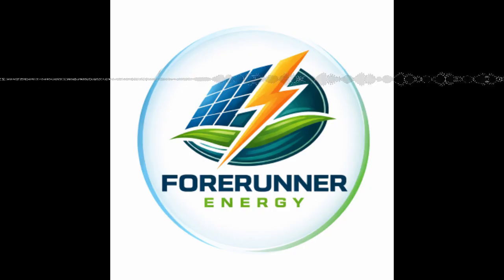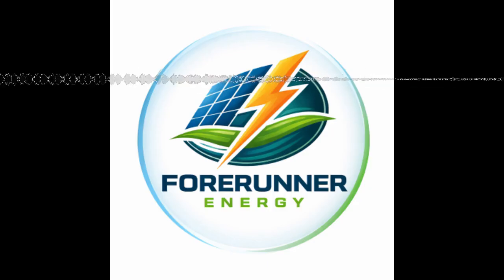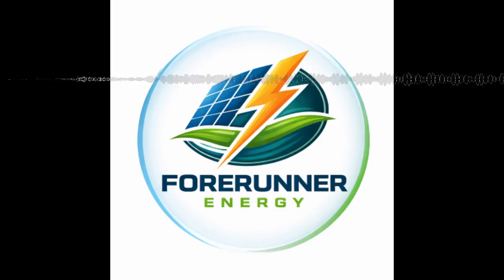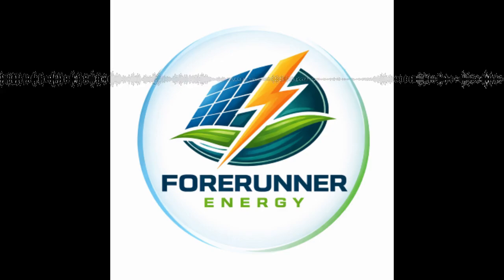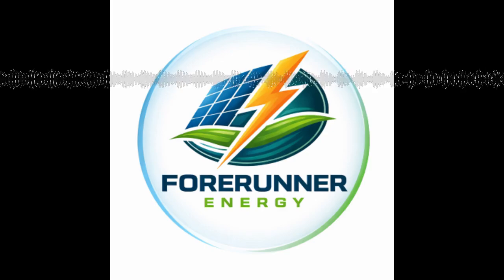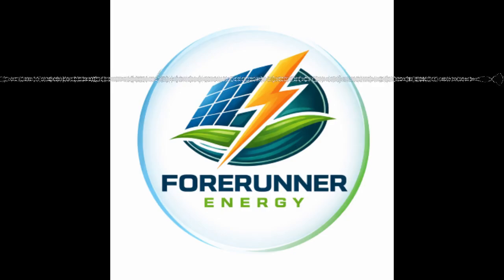Let's pivot to the feature that truly differentiates hydrogen from batteries: long-duration autonomy. Batteries are excellent for short bursts, minutes, maybe a few hours, but they struggle with multi-day resilience. This is the crucial differentiator. The system's storage duration spec is 24 hours minimum, extending all the way up to 168 hours, a full week of continuous power. That's what changes the game for critical loads. You're prepared for a prolonged grid failure, not just a momentary hiccup.